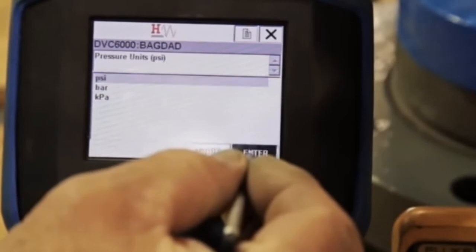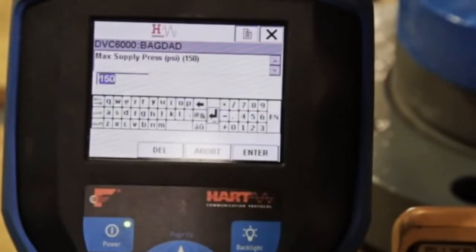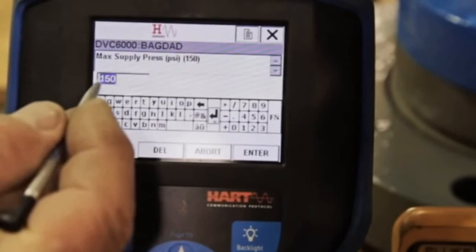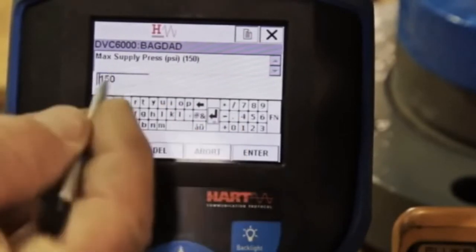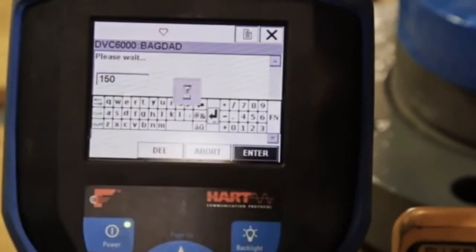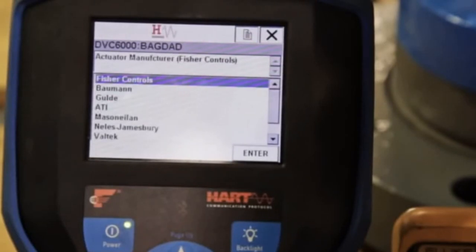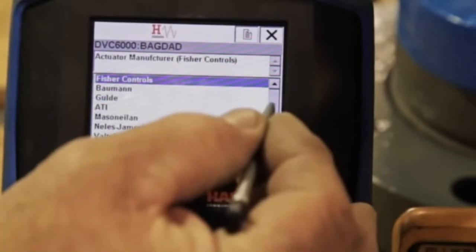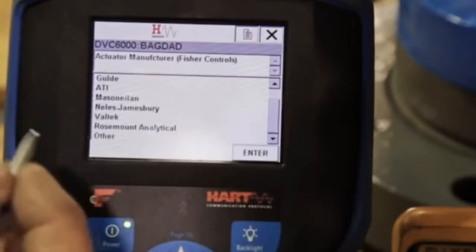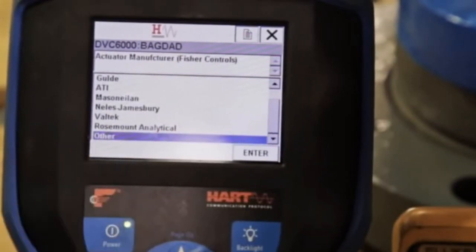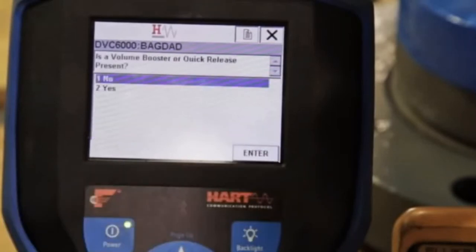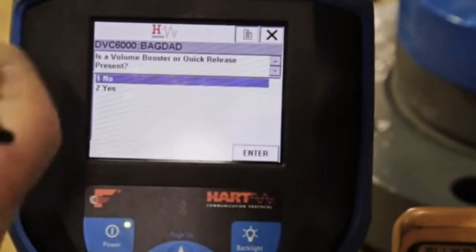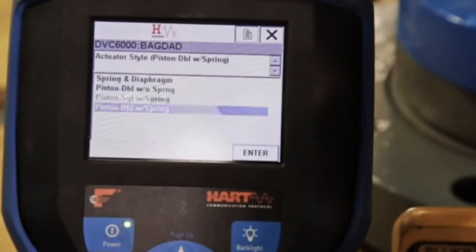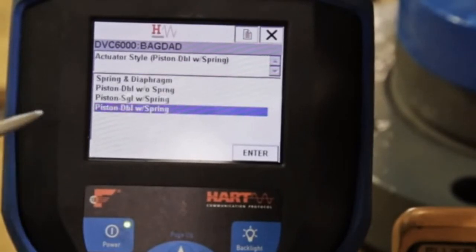Select the appropriate unit of pressure. Input the maximum air supply pressure. For the next set of questions, choose the features that best represent your equipment configuration. For this example, we'll select Other for actuator manufacturer. This actuator does not have a volume booster or quick release, so we'll select No. Piston double with spring.